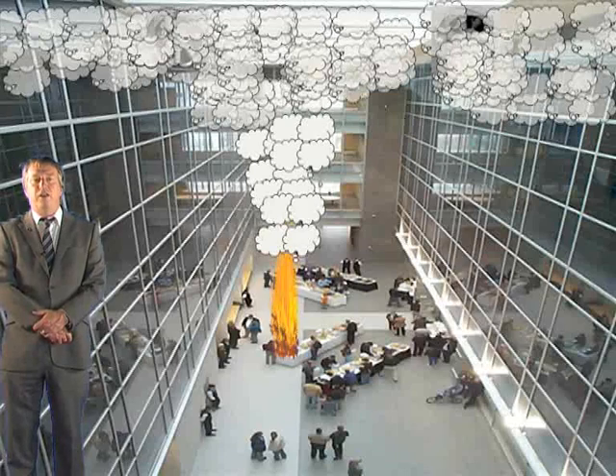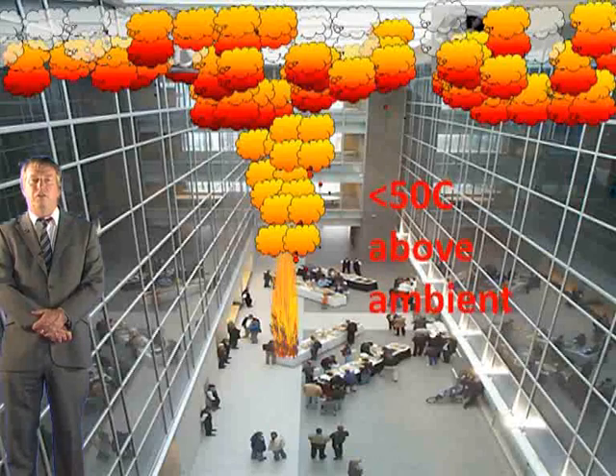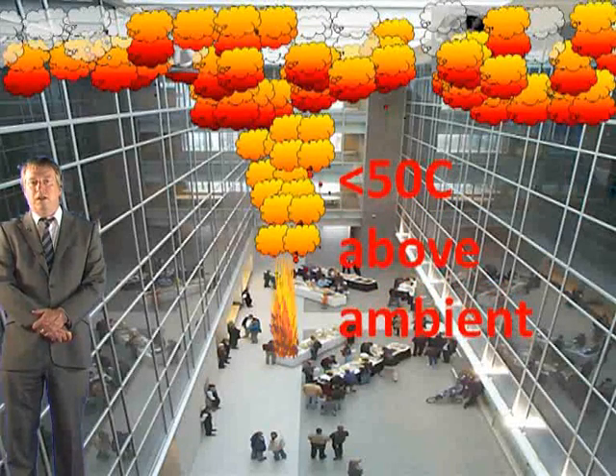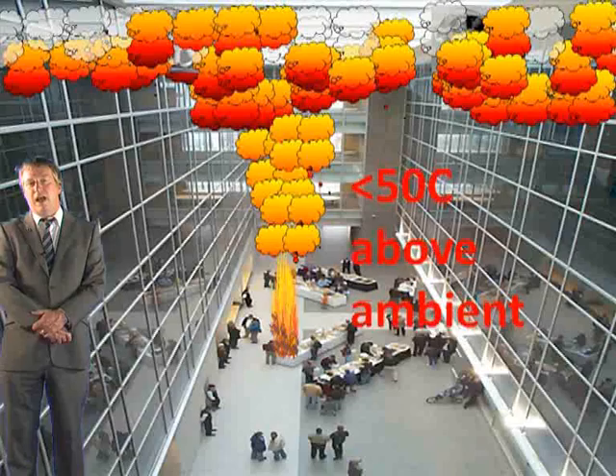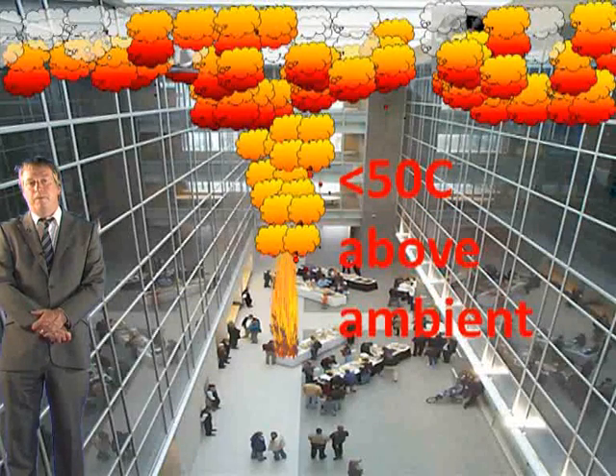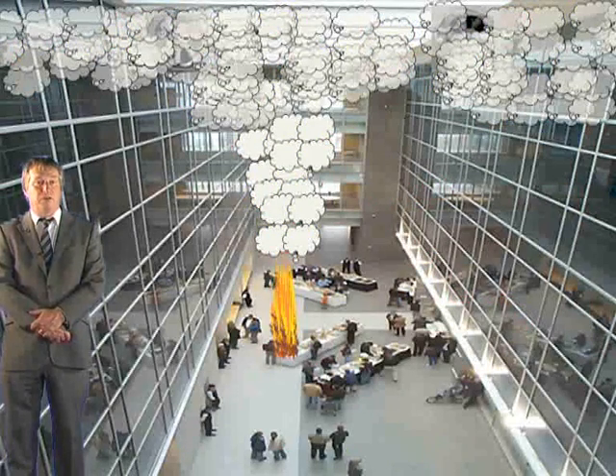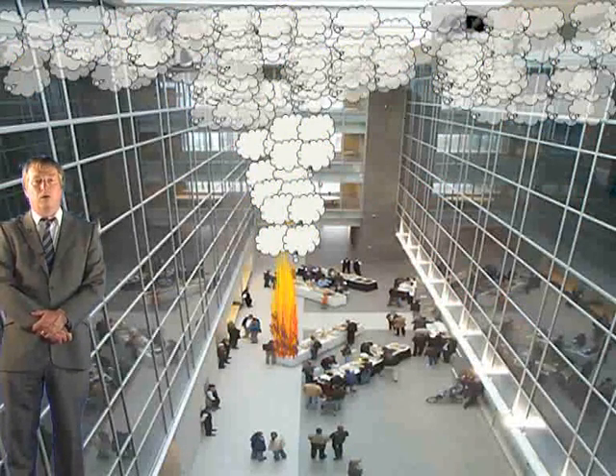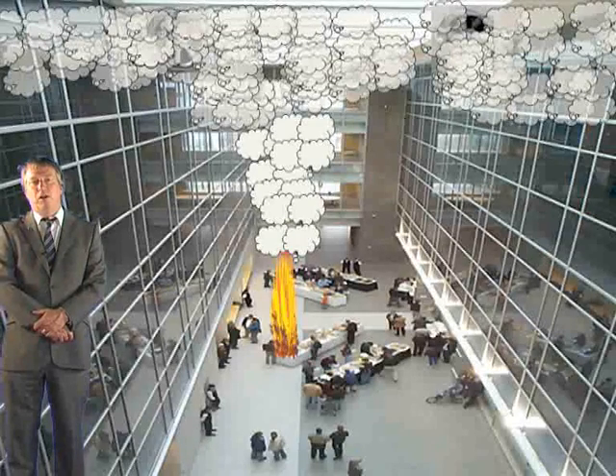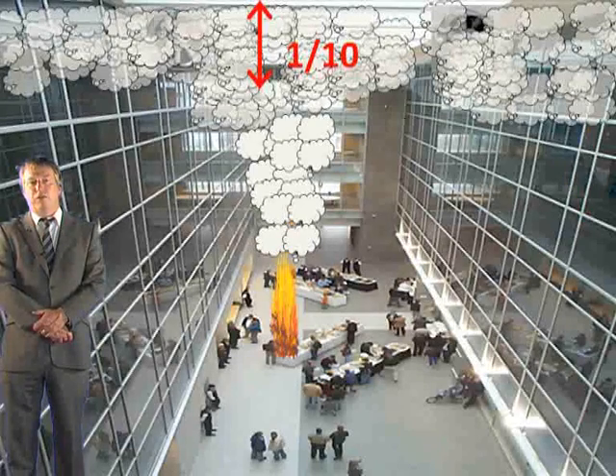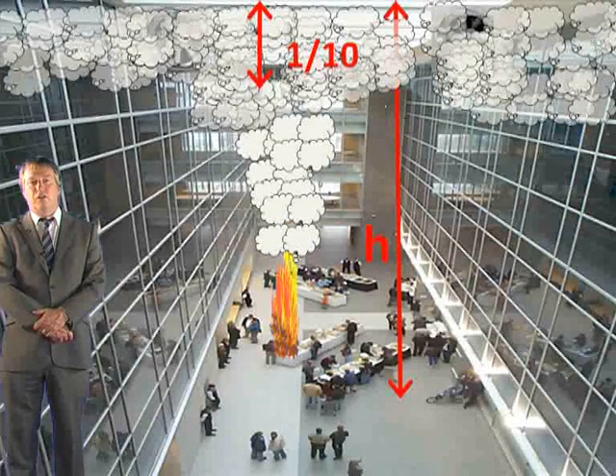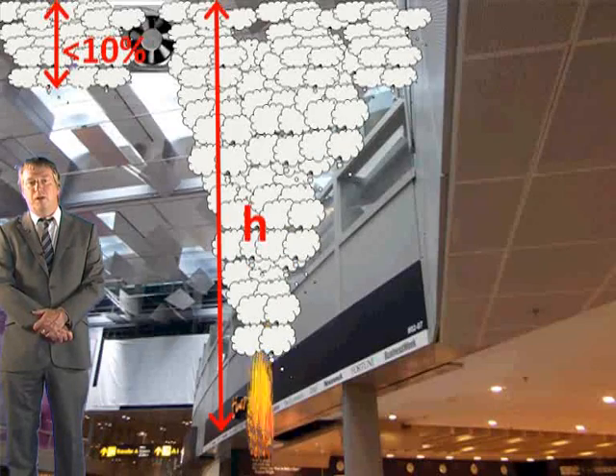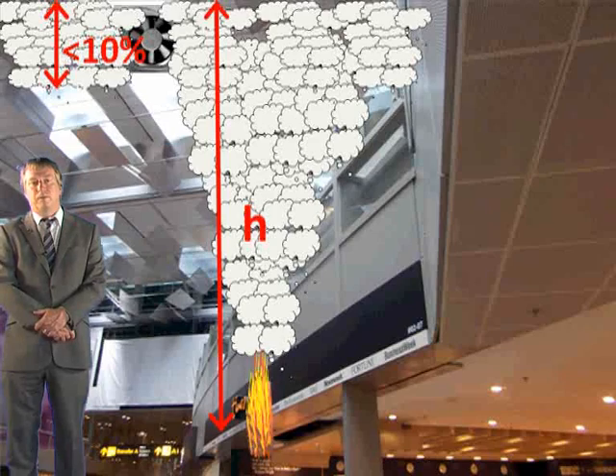You should note that where the predicted layer temperature is less than 50 degrees Celsius above ambient temperature, it may be a wise idea to add half a metre to each minimum value mentioned. This is guidance that is given in some documents but not all. You should also be aware that the buoyant layer in the smoke reservoir should not be designed to be less than 1/10 of the floor to ceiling height for fires directly below the smoke reservoir, or less than 1/10 of the height from the spill edge to the ceiling for spill plumes.